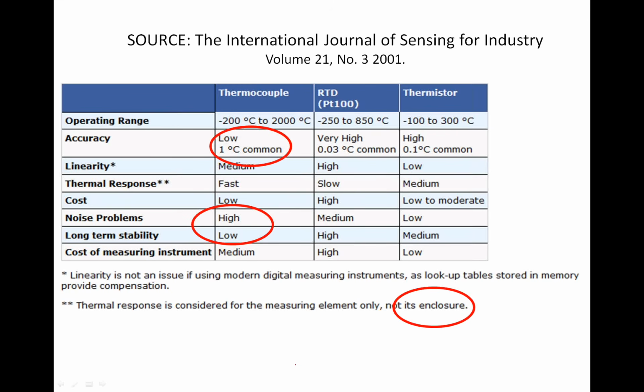All right? When you get into a thermocouple also, you have to consider the enclosure that it's in. Everybody goes, oh, K-type thermocouples are so fast. Well, yeah, they are. They really are with a bead-type thermocouple probe. But you also have to remember if we incorporate that bead into a clamp probe, it's going to slow that thing down. It's going to make it more comparable to a thermistor. So, well, the beads are very quick. They're really only suitable for measuring airflow, not for really measuring pipe temperatures.